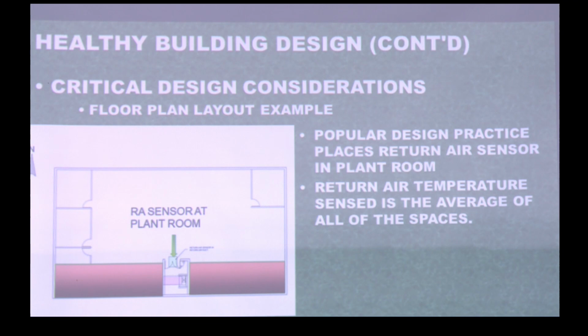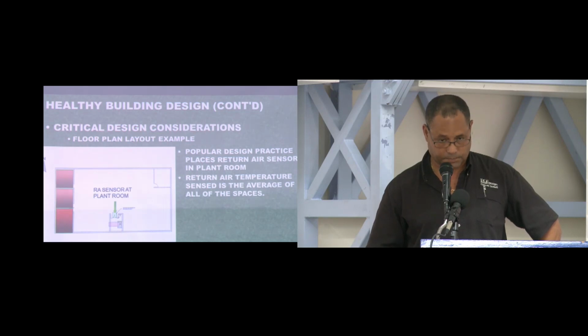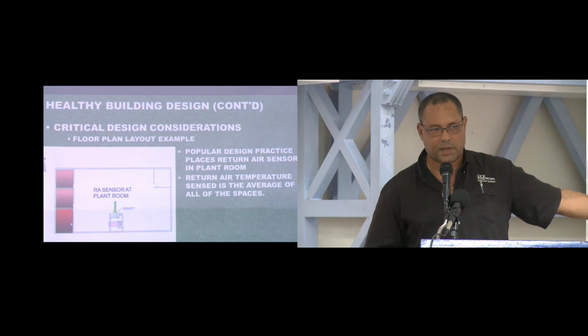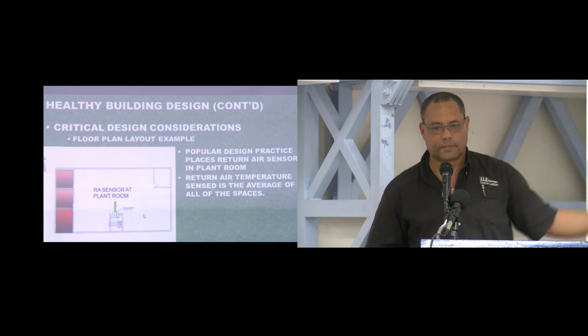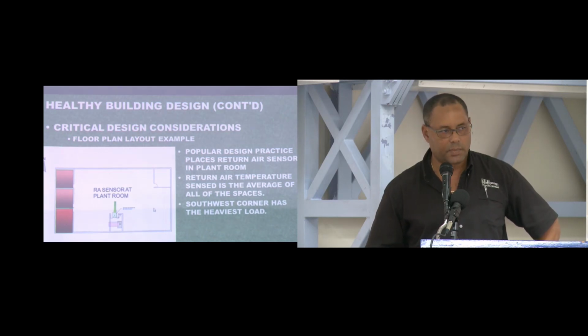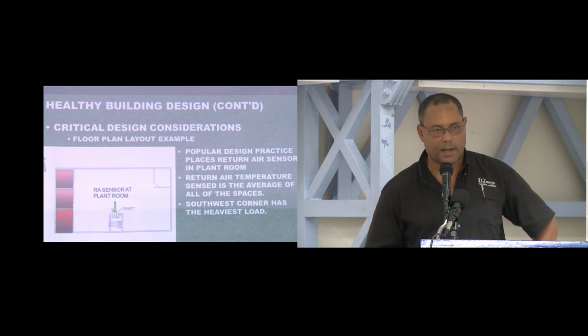As the day goes on, usually in summertime, the sun is more on a southerly path. So your south face gets most of the load. In the afternoon in the west, you've got the load on the west of the building. Where your corner office, down here, southwest corner, still has a load from the south, and he's now getting the load from the west. So he's got the heaviest load in the building. But our sensor is back at the plant room, and it's telling the equipment that it's still 72 degrees. The person in the corner office doesn't agree, but there's nothing that the system can do about it.